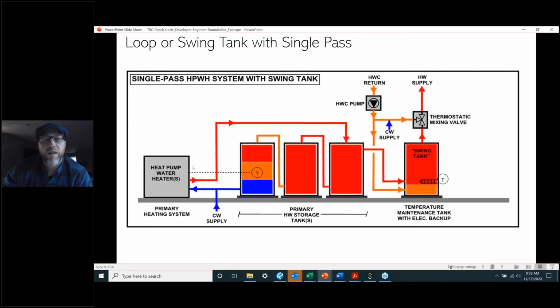The key point with single pass heat pump water heaters is to not let your heat pump see the hot water circ temperature. Decoupling this will preserve the efficiency of your single pass device for your primary storage. Remember, this is the majority of the load.